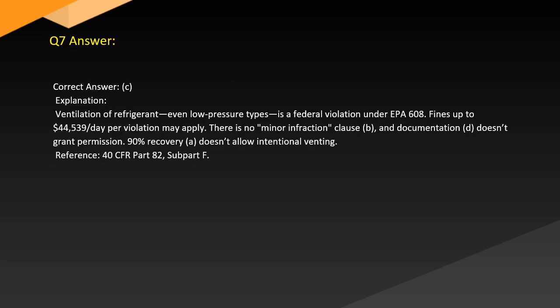Answer. Correct answer, C. Explanation. Venting of refrigerant, even low-pressure types, is a federal violation under EPA 608. Fines up to $44,539 per day per violation may apply. There is no minor infraction clause, B, and documentation, D, doesn't grant permission. 90% recovery, A, doesn't allow intentional venting. Reference 40 CFR Part 82, Subpart F.